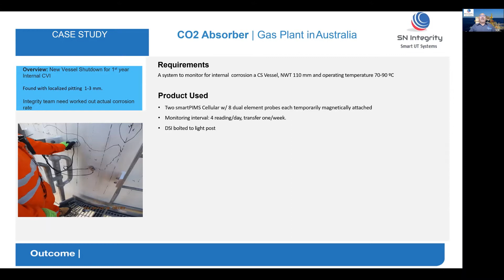So they mapped out the lowest areas and contacted us with the following requirements: a system for a carbon steel vessel, very thick, nominal wall thickness was 110 millimeters, operating at a temperature range between 70 to 90 degrees C. So we proposed to use 2 smartPIMS Cellulars with 8 dual element probes, temporarily magnetically attached, with 4 readings per day and transferring data once a week, with the DSI bolted to an existing light post nearby in the tower.